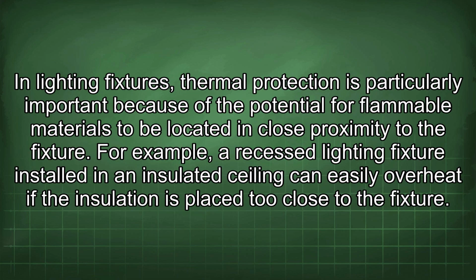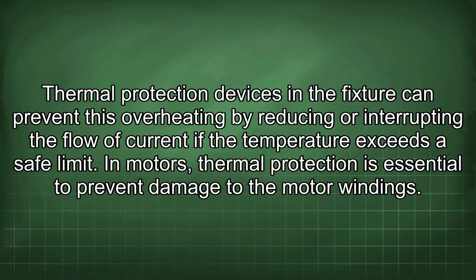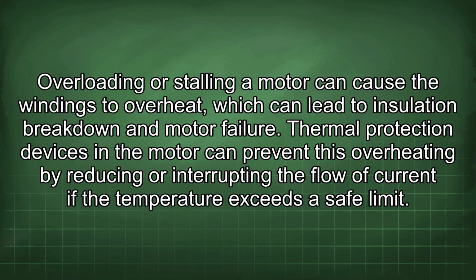In lighting fixtures, thermal protection is particularly important because of the potential for flammable materials to be located in close proximity to the fixture. For example, a recessed lighting fixture installed in an insulated ceiling can easily overheat if the insulation is placed too close to the fixture. Thermal protection devices in the fixture can prevent this overheating by reducing or interrupting the flow of current if the temperature exceeds a safe limit. In motors, thermal protection is essential to prevent damage to the motor windings. Overloading or stalling a motor can cause the windings to overheat, which can lead to insulation breakdown and motor failure.